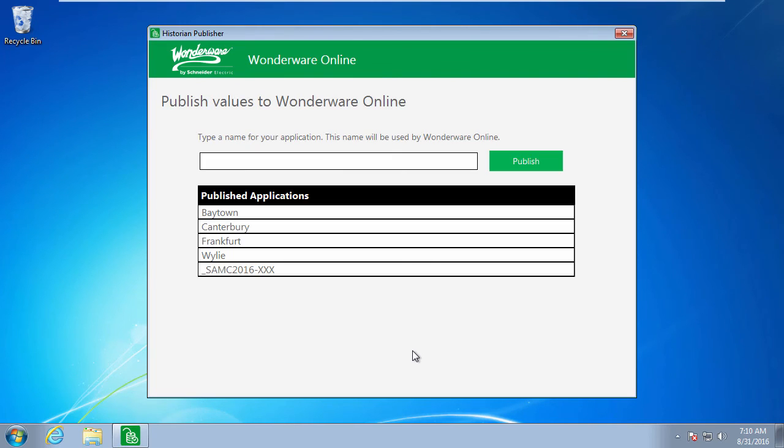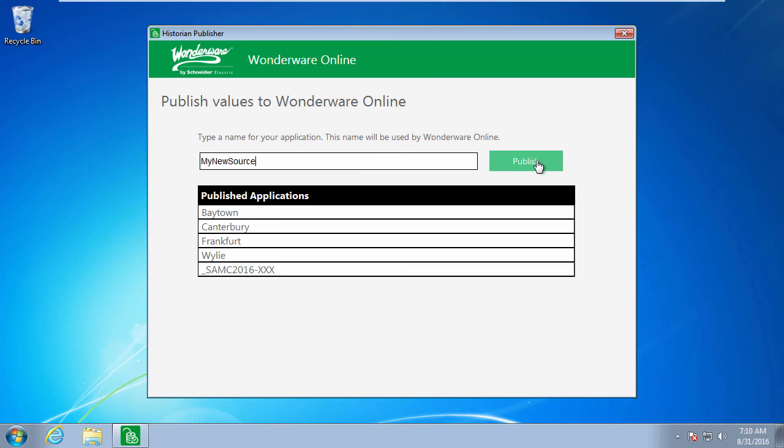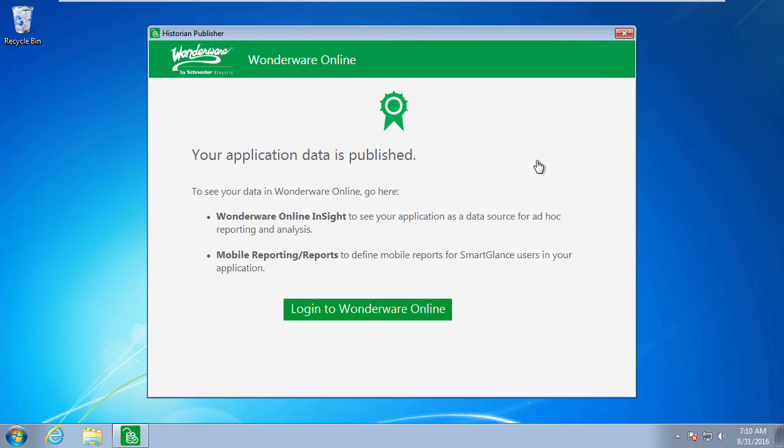And I'm going to register a new data source. A data source represents an OPC server, and it's a name that's going to be meaningful to me in my applications, probably something other than my new source. When I click Publish, this source gets registered online and immediately sets up a subscription to the OPC server and begins sending data. It is that simple.